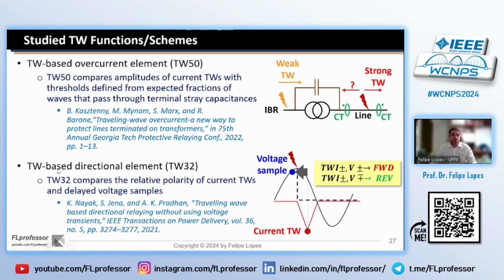There is a very interesting traveling wave-based directional element, which I considered here. It is not exactly the one that has been implemented in off-the-shelf devices, but I do believe that this function is very promising, because it compares the relative polarity of current traveling waves with the voltage sample, some samples before the detection of the current traveling wave. By doing so, they overcome the need of measuring transients by means of CVTs, and they take the reliable measurements from the CTs. Just by comparing the polarities of these wavefronts, they can distinguish forward from reverse faults. For forward faults, the voltage sample and the current traveling wave present the same polarity, and for reverse faults, they present opposite polarities. And the solution you can find in this paper here.